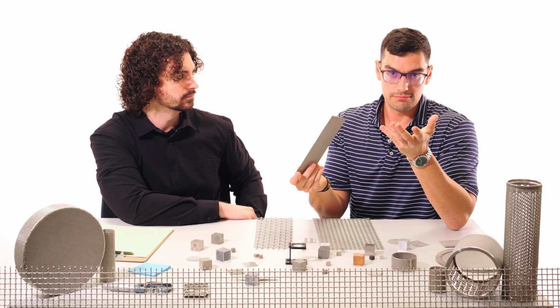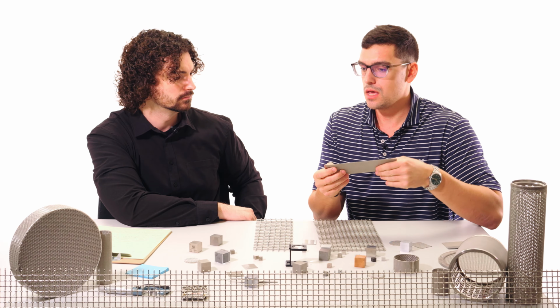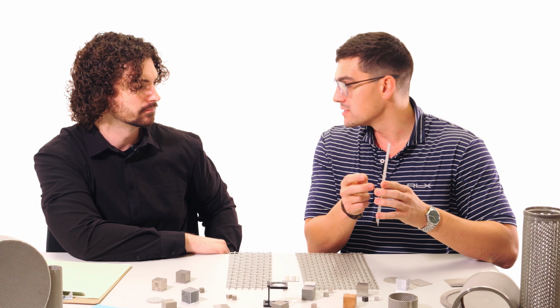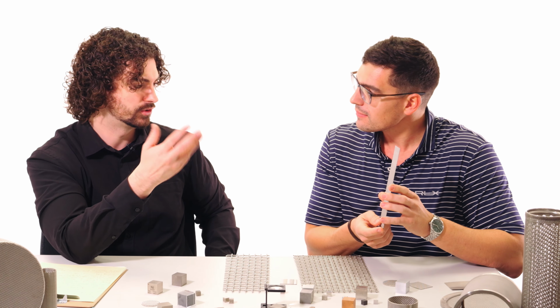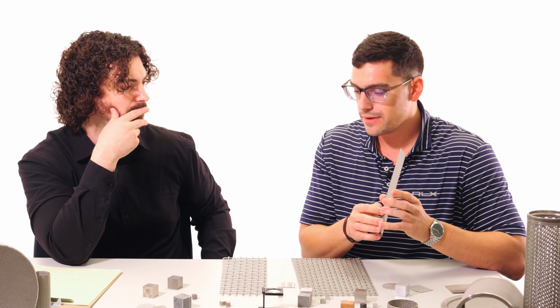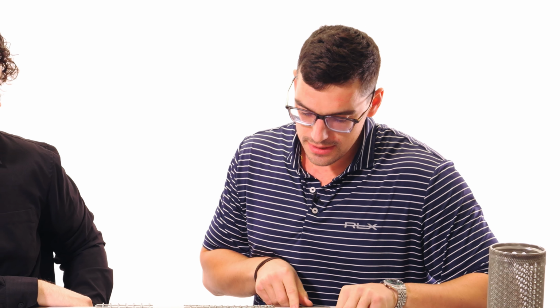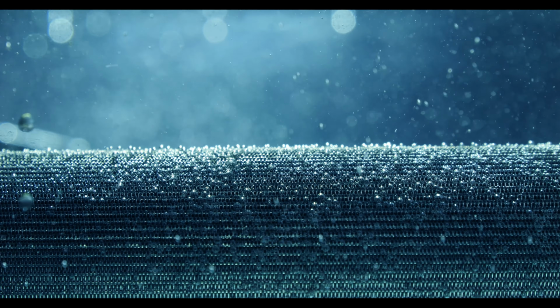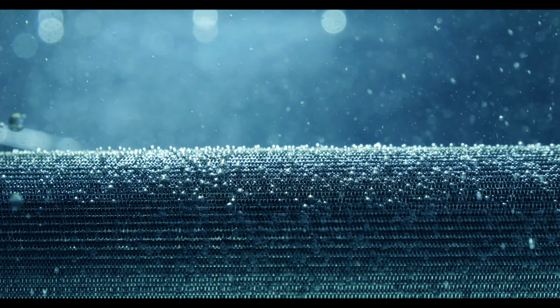Another way is mechanical cleaning, which is a little bit more labor intensive, where you would physically remove your filter, and then you would use a vibrating application to help dislodge the particles that are tough inside. Oh, like an ultrasonic cleaner? Ultrasonic would work great, or there are even hand tools where they're using a brush on the outside of the surface, and that can sometimes get in those pores. Another option, if the particles are super hardened and lodged inside and back flushing and mechanical cleaning haven't worked, is chemical cleaning. That's where you're using a detergent or an acid that will really break down those tough particles and allow you to fully get rid of them. That's more of a last ditch effort, I would say.